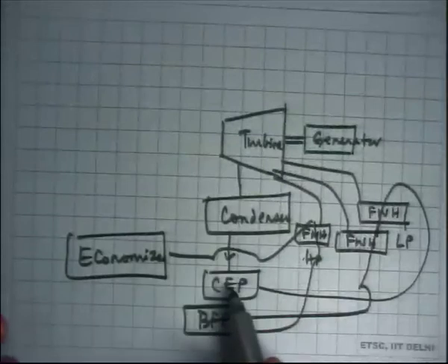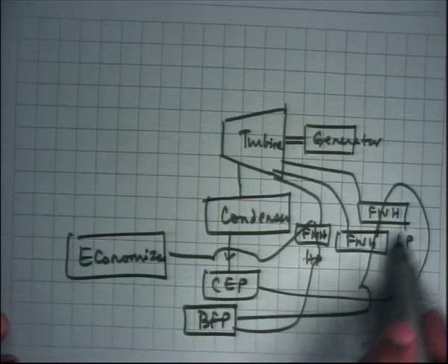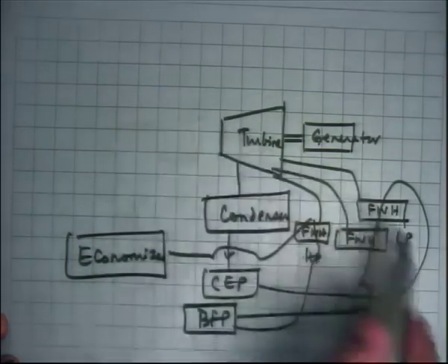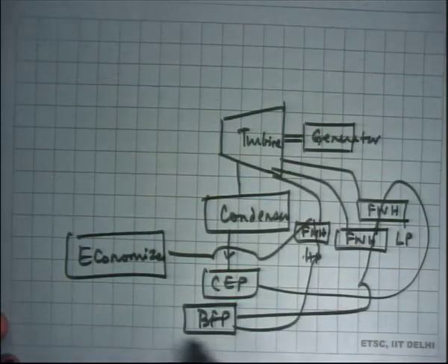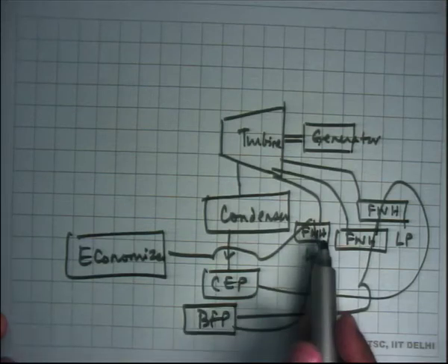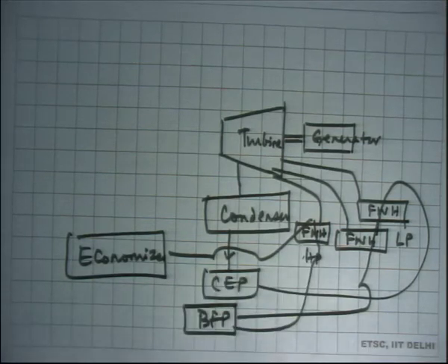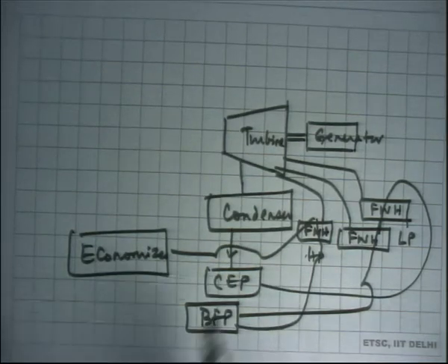The water from the turbine goes to the condenser. From the condenser it goes to the condensate extraction pump, goes as feed water to the LP heaters where the LP turbine steam is condensed. Okay. Then it goes to the boiler feed pump. So, the water becomes a high pressure water now, and then it goes to the HP heaters because HP heater also has steam at a higher temperature. Okay. So, from the HP heater the water goes very close to the saturation point, and then it goes to the economizer. Economizer is the tail end of the flue gases.